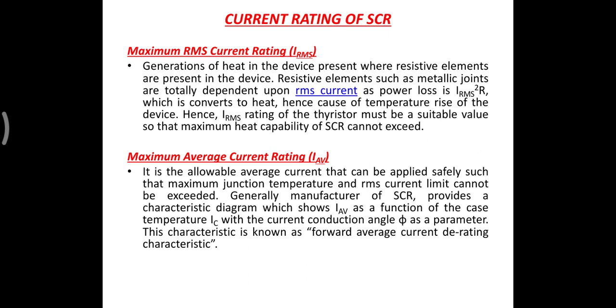So the specifications mentioned on the data sheet provide the relationship between temperature and average current. So we have to consider all these things while selecting the SCR. So our SCR must meet the RMS current rating within specific temperature limits.